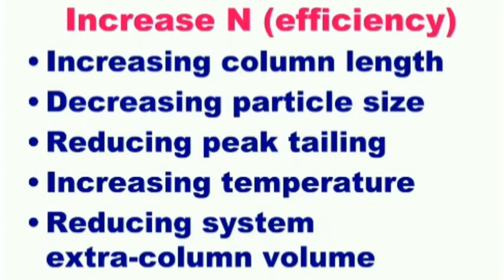Now I will tell you how to improve resolution in HPLC. Number 1: increase number of efficiency. You can increase efficiency by increasing column length, decreasing particle size, reducing peak tailing, increasing temperature, and reducing system extra column volume.